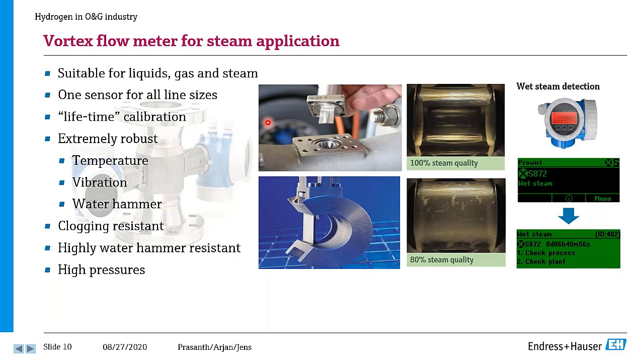Number of the Vortex flow meters that come back to our factory for recalibration. We found that there is high stability in terms of our factory calibration, and only in applications where there is high erosion or corrosion possible and there is a reduction in the inner diameter of the shedder bar, those are the areas where we see some shift. But in terms of standard steam, gas, other liquid applications, lifetime calibration.